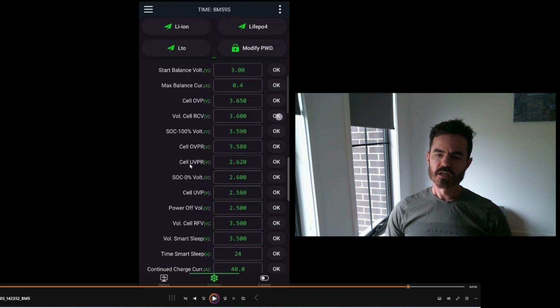Down here we've got cell under voltage protection return at 2.62 volts. That just means once our under voltage protection at 2.58 volts triggers, so once the battery sits below that, it'll stop any discharging. But then once it gets back over 2.62 volts, it'll start allowing discharging again.